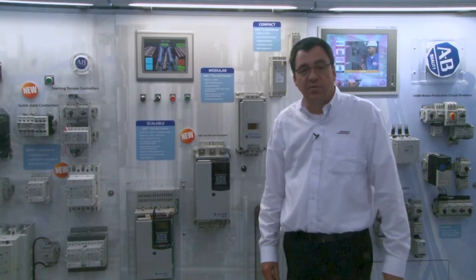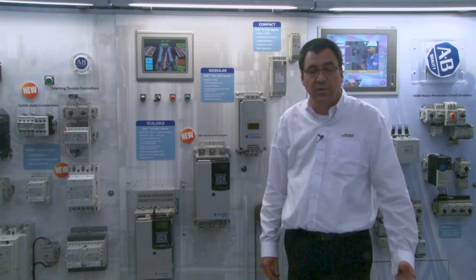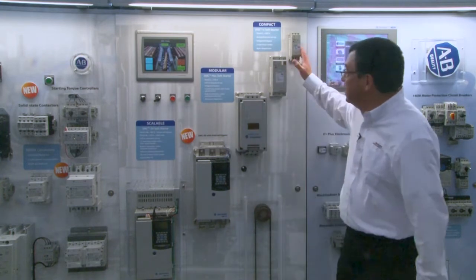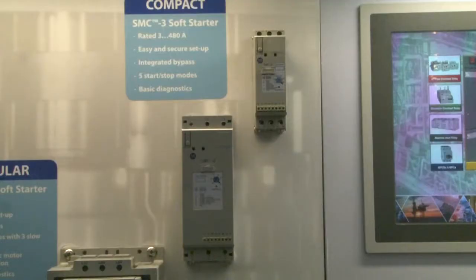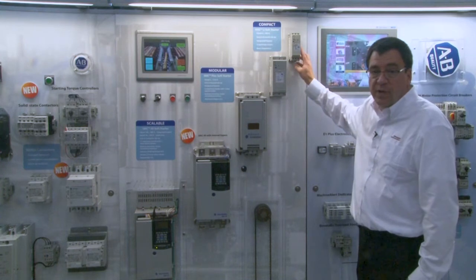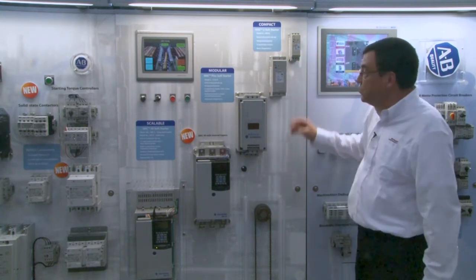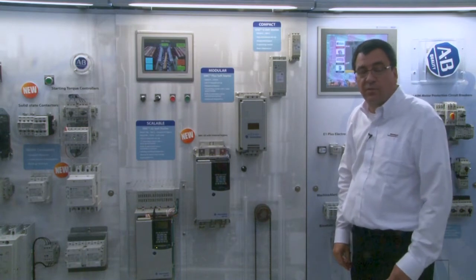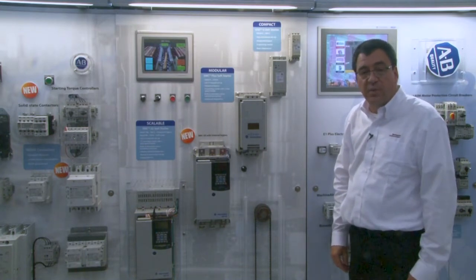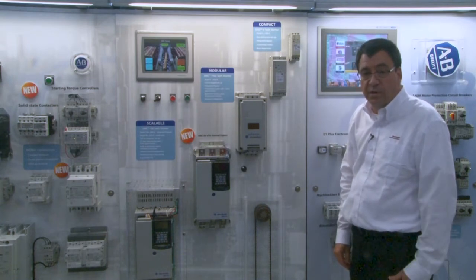We have three SMC families: the SMC 3, the Flex, and the 50, and those are known as our compact, modular, and scalable offerings. The SMC 3 is our compact offering. This is great for retrofits due to its small, industry-leading size. For example, this Frame 1 unit goes from 3 amps out to 37 amps. The SMC 3 is offered from 3 amps to 480 amps, has five starting and stopping modes, internal bypass, and overload protection.